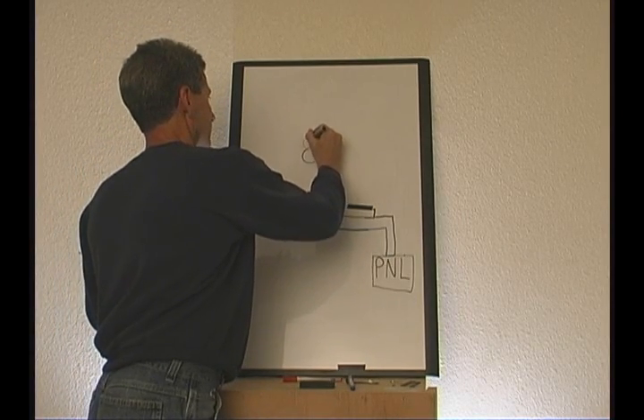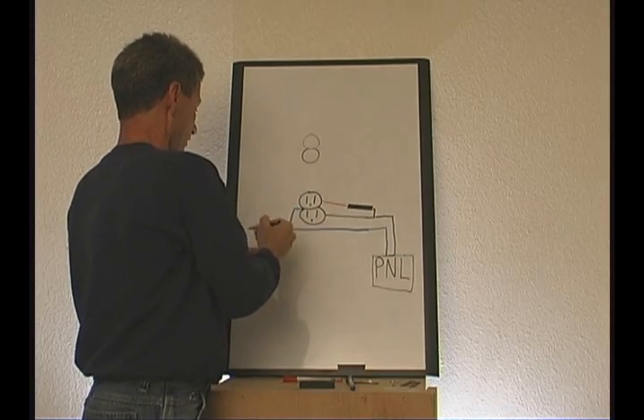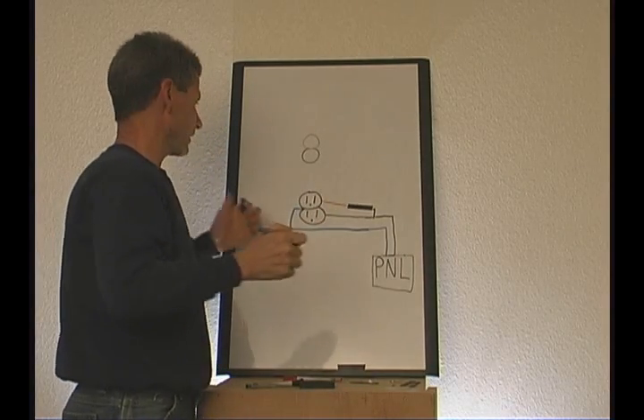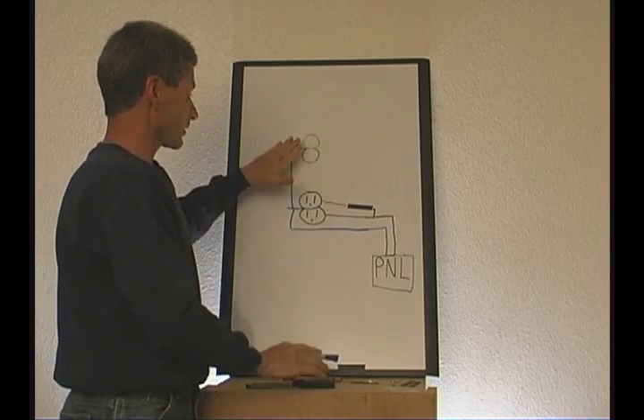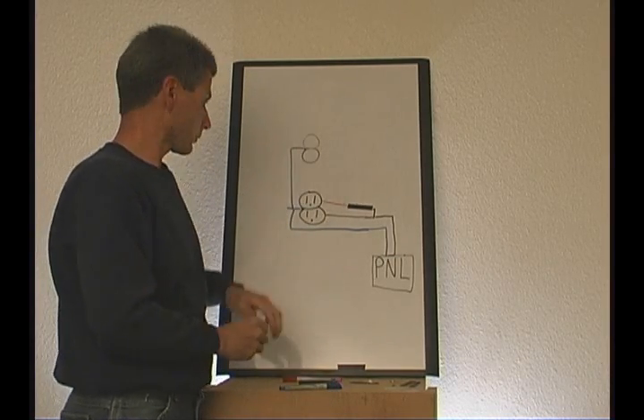Let's put our plug in here. The neutral is the easy part. The neutral just pigtails here and goes up again. If this is going to be half-switched, we have to break the tab.